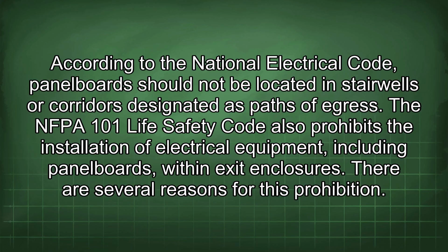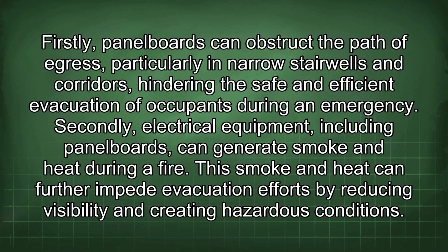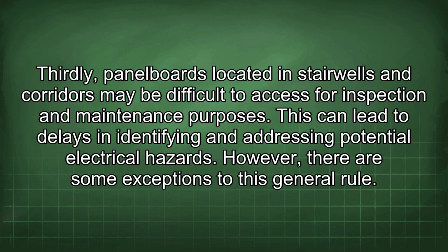There are several reasons for this prohibition. Firstly, panelboards can obstruct the path of egress, particularly in narrow stairwells and corridors, hindering the safe and efficient evacuation of occupants during an emergency. Secondly, electrical equipment, including panelboards, can generate smoke and heat during a fire. This smoke and heat can further impede evacuation efforts by reducing visibility and creating hazardous conditions. Thirdly, panelboards located in stairwells and corridors may be difficult to access for inspection and maintenance purposes. This can lead to delays in identifying and addressing potential electrical hazards.